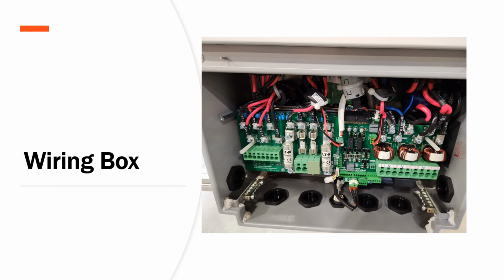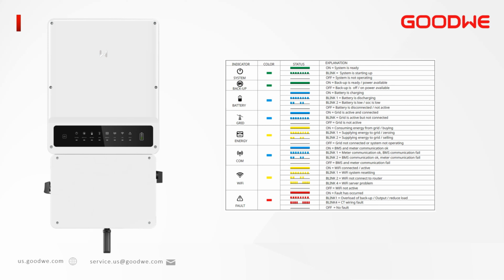I have removed the plastic cover from the photo, but remember, this is in most cases not necessary. As I mentioned earlier, the rapid shutdown module is built in from the factory. We offer options from Tigo, APS, and soon to launch our GoodWe transmitter. For all of these, you have to specify which you prefer from the distributor. Note that the PV rapid shutdown system must be sourced separately. If you are installing this inverter on a site that doesn't require rapid shutdown, you will need to disable the transmitter. In this case, all you need to do is disconnect the 12-volt power supply to the transmitter.